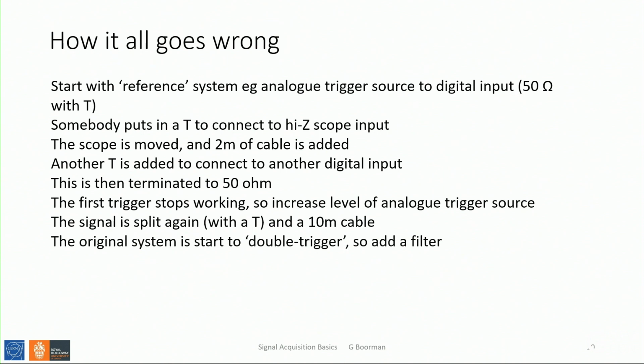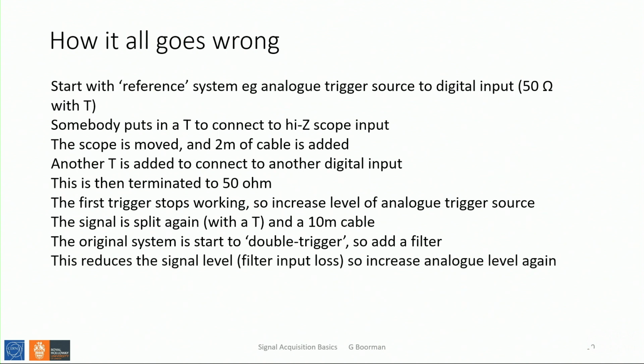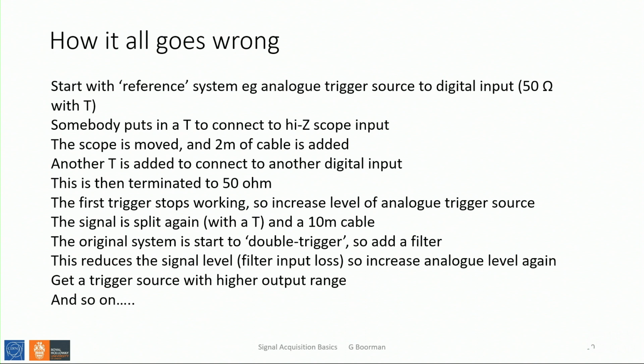So, bright idea, let's add a filter. It's been done, you might laugh, but it has been done. This reduces the signal level again because of the filter's input loss, so you increase your analog output level again. You're already at the limit. You need the next analog source, so you need a higher input or output range for it. And so it goes on.